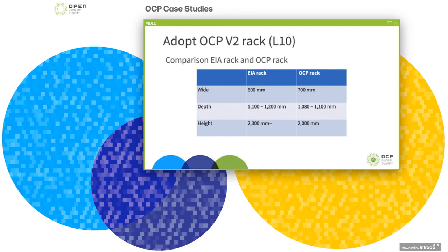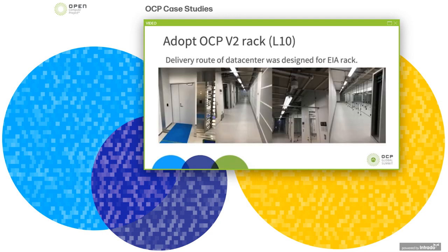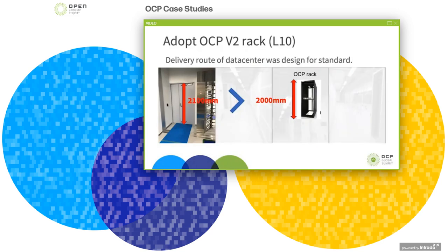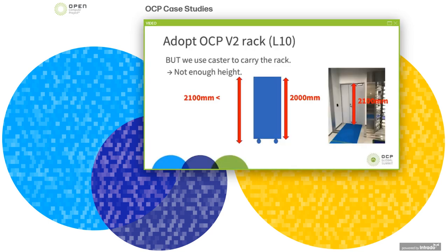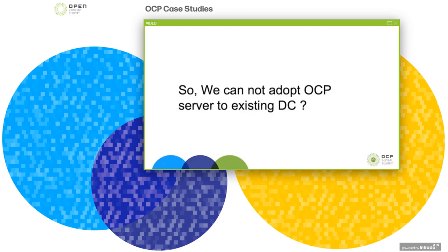Although the EIA rack is higher than the OCP rack, it did not need to be carried as a fully assembled unit. Let's look at the delivery route again. Before carrying, we investigated whether we could do the L10 adoption. The answer was no. Which part do you think caused the problem? It's the door - we wanted to use casters to carry the rack, but there wasn't enough height. So does that mean we can't adopt OCP servers in our existing data center?